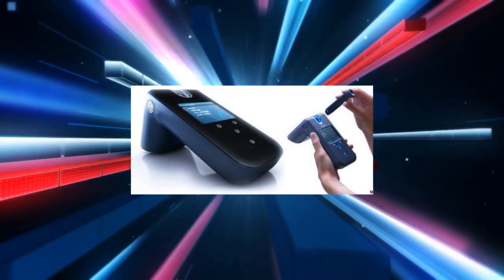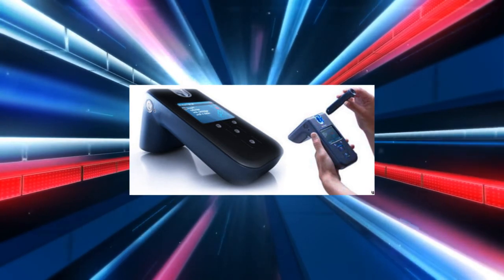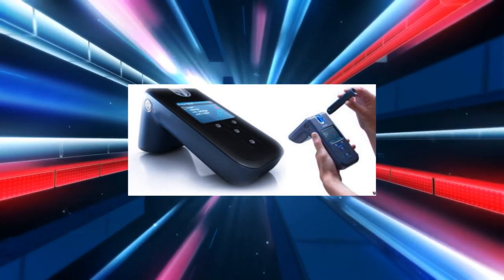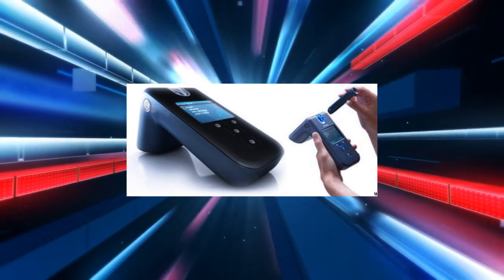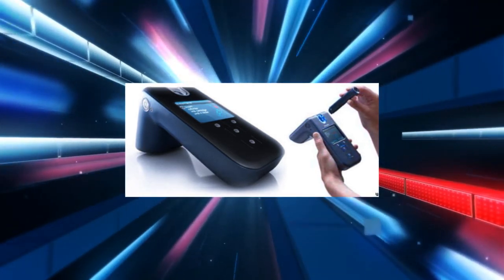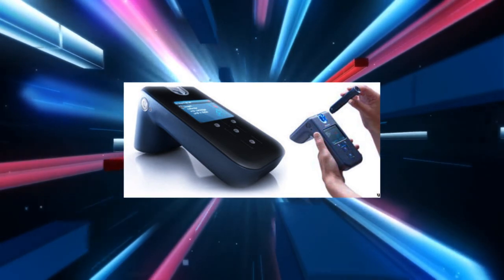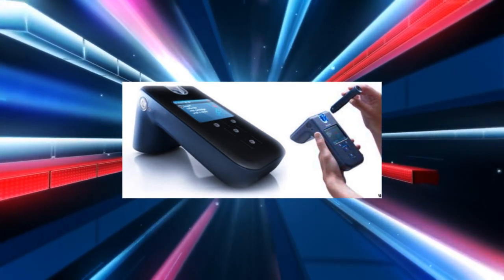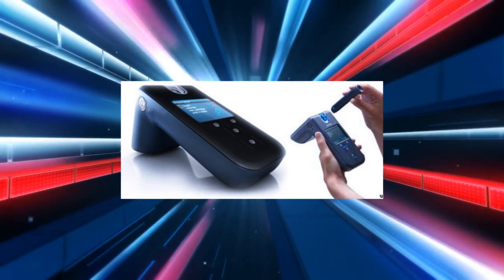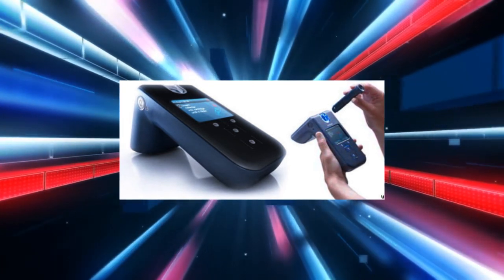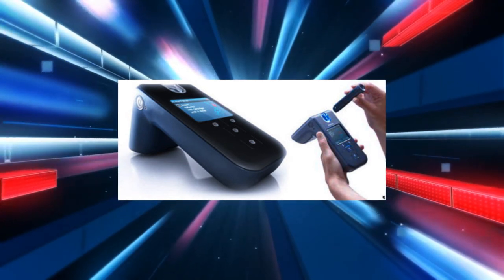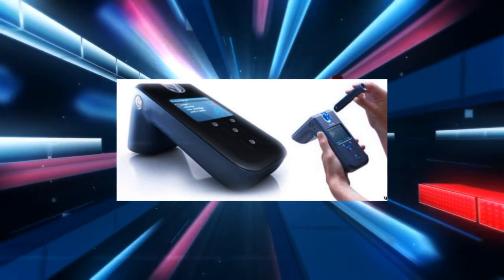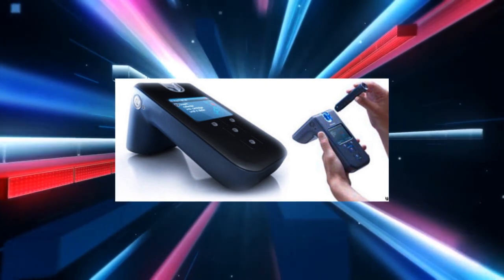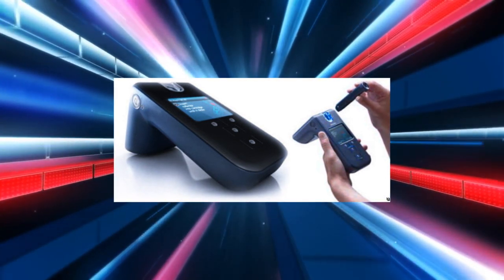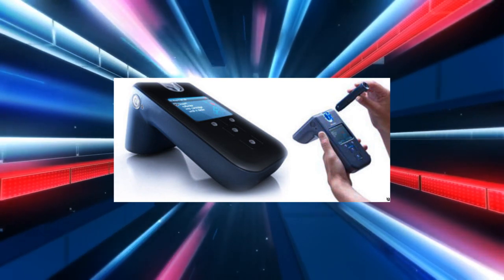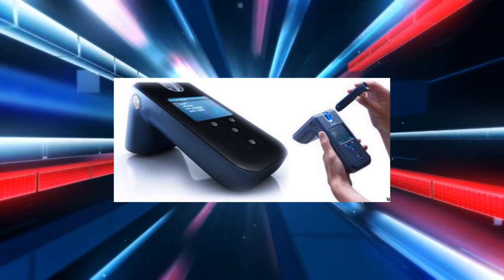Drug detector. Stanford engineers create experimental technology to monitor and maintain drug levels in the body. The new technology has three basic components: a real-time biosensor to continuously monitor drug levels in the bloodstream, a control system to calculate the right dose, and a programmable pump that delivers just enough medicine to maintain a desired dose. The sensor contains molecules called aptamers that are specifically designed to bind a drug of interest. When the drug is present in the bloodstream, the aptamer changes shape, which an electric sensor detects. The more drug, the more aptamers change shape.